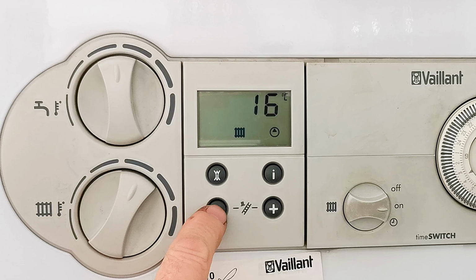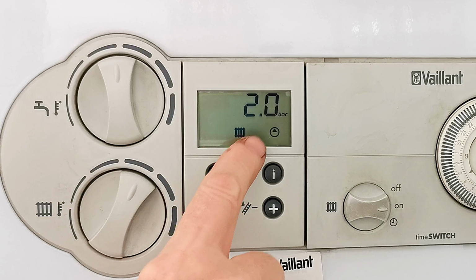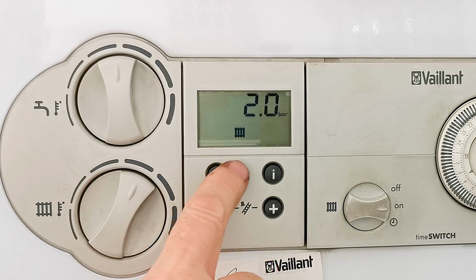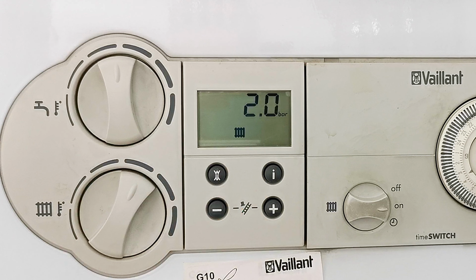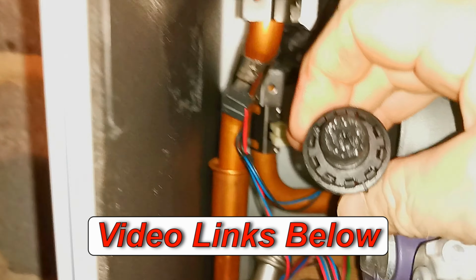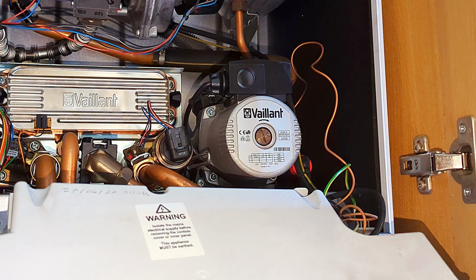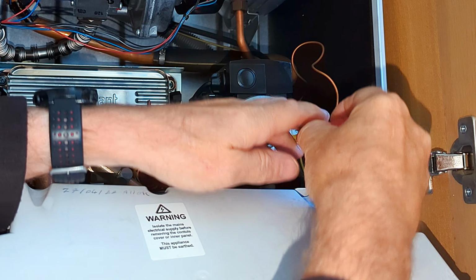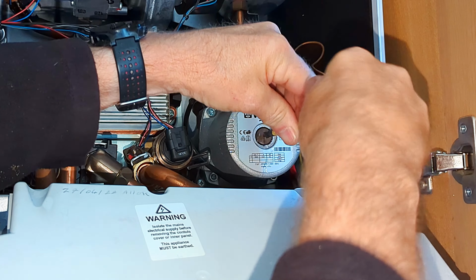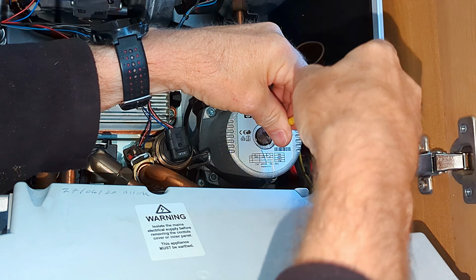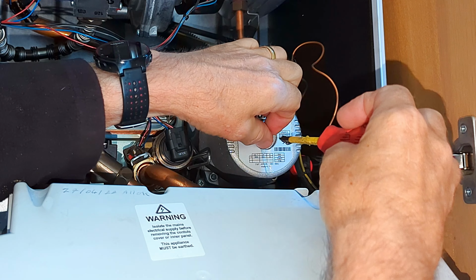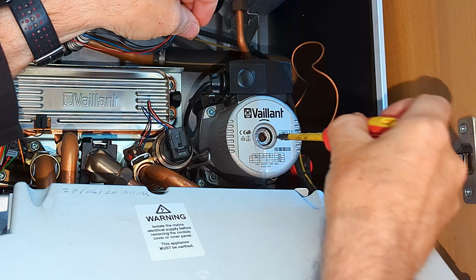Now you can do this check with the boiler cover on. After the click on the relay, if you hear the pump humming, but you don't see a pressure rise on the display, then you most likely got a faulty pressure sensor and not a faulty pump. Now the only real way to check if a pump is running is to actually physically check it. And to do that, we undo this large screw on the back of the pump head here, put a screwdriver inside, and if the pump is running well, you'll hear a sound like this.